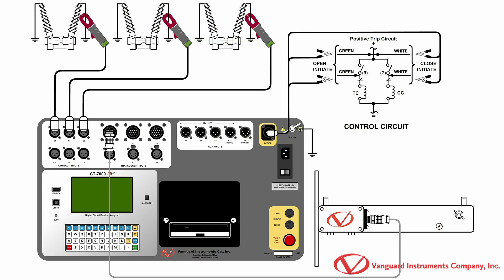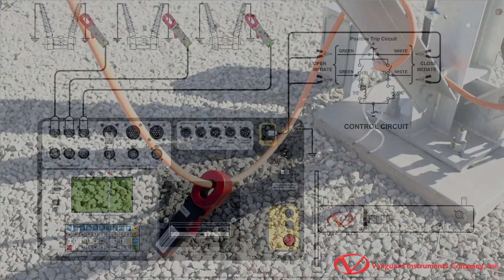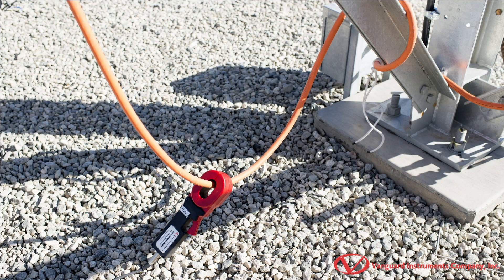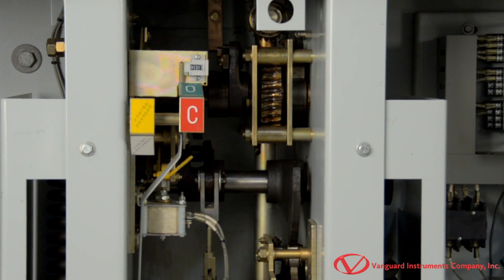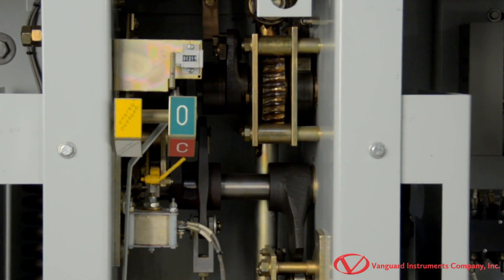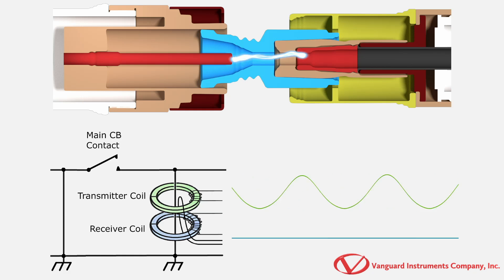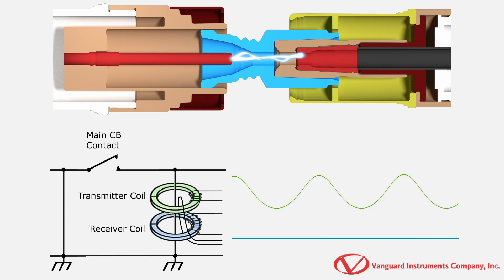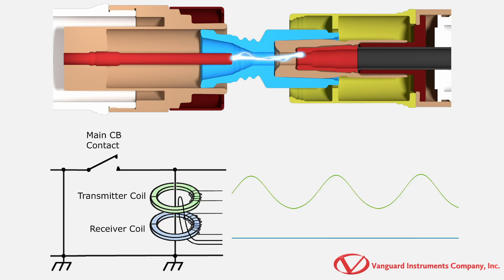Vanguard's dual ground testing of circuit breakers requires the user to connect the measurement probe on one side of the grounding cable in each phase as shown here. Vanguard's timers use a novel patent-pending technique for the open and closed timing measurement of the main contacts. With this technique, a high-frequency voltage signal is injected by the transmitter embedded in the measurement probe.